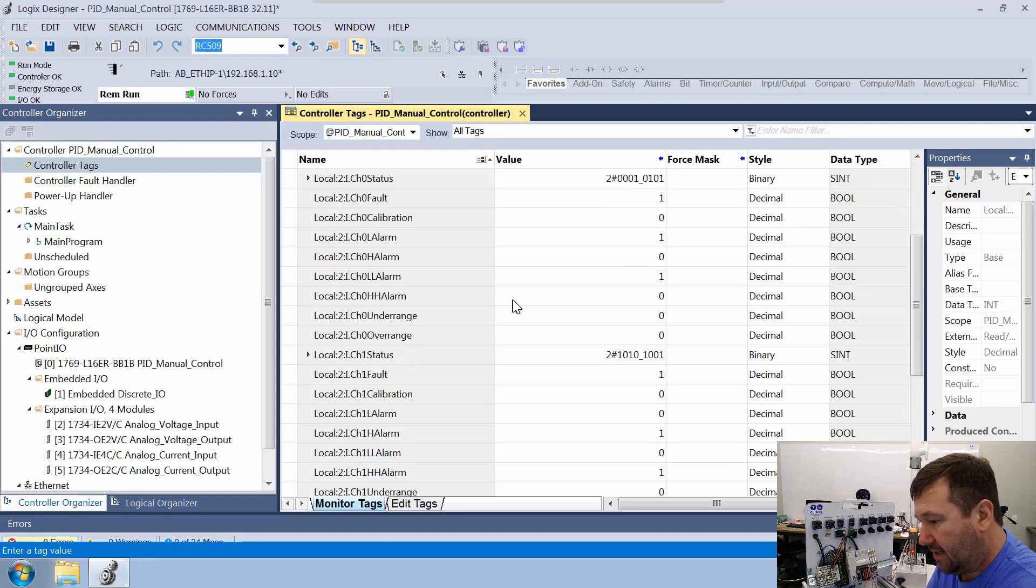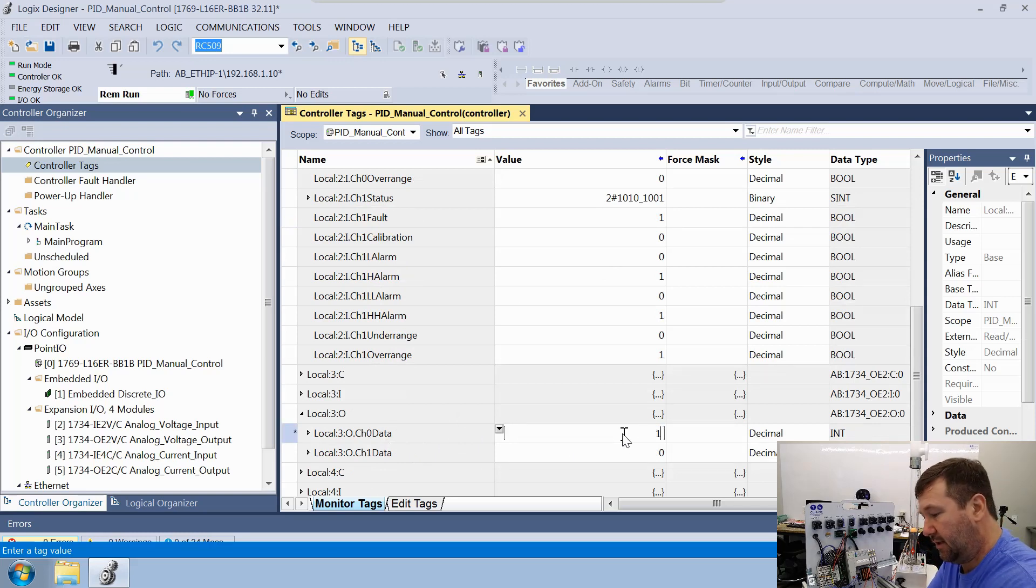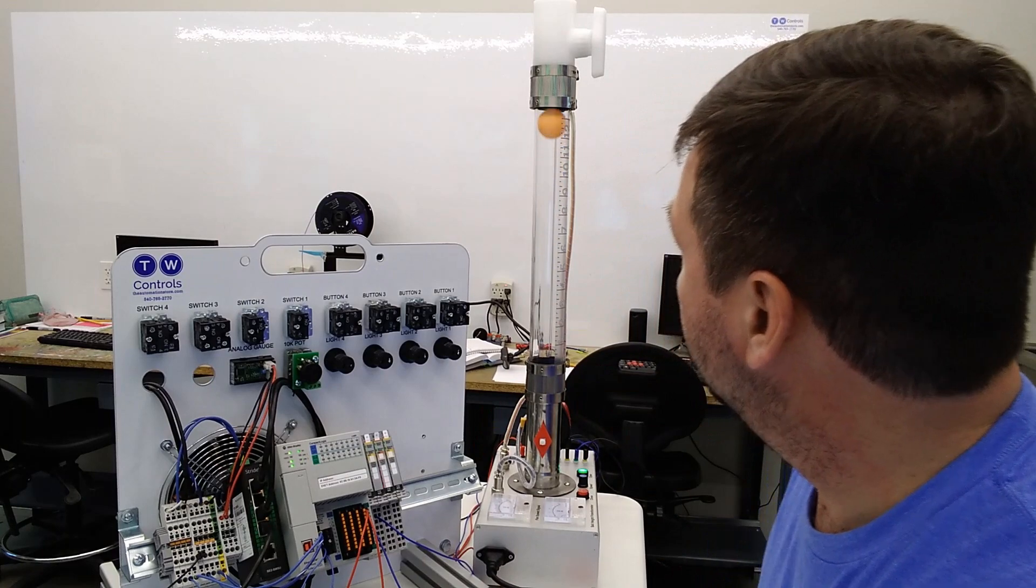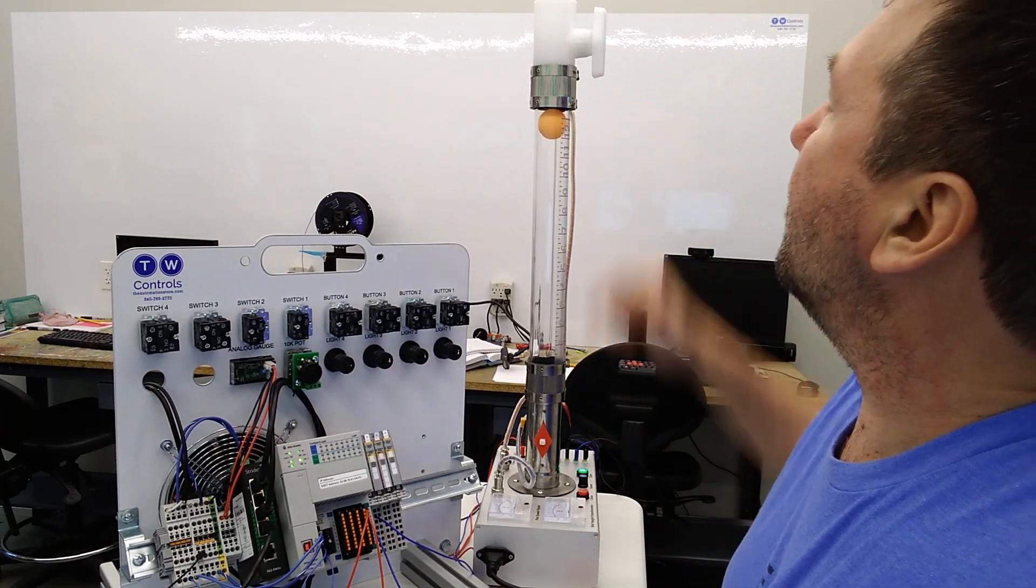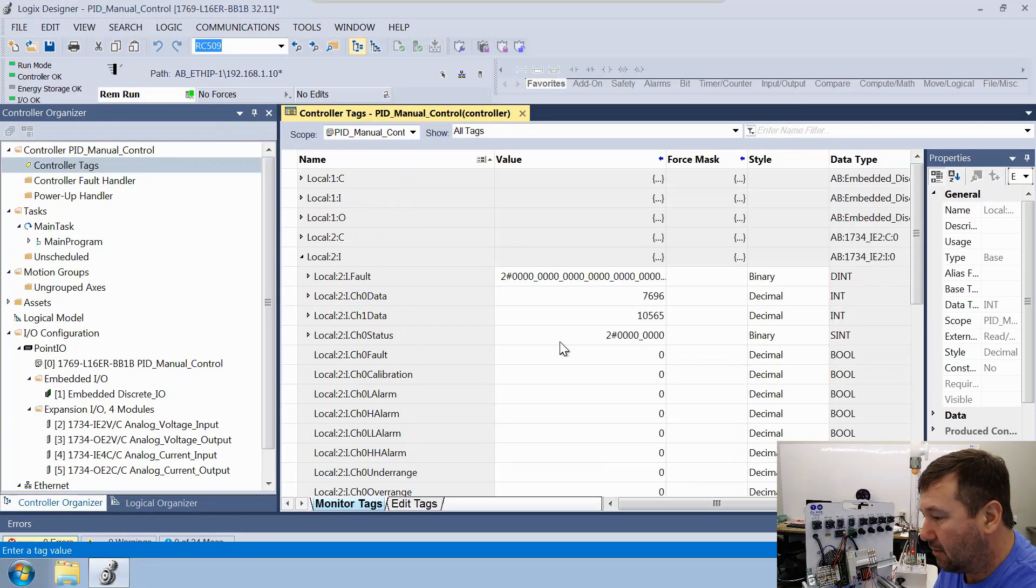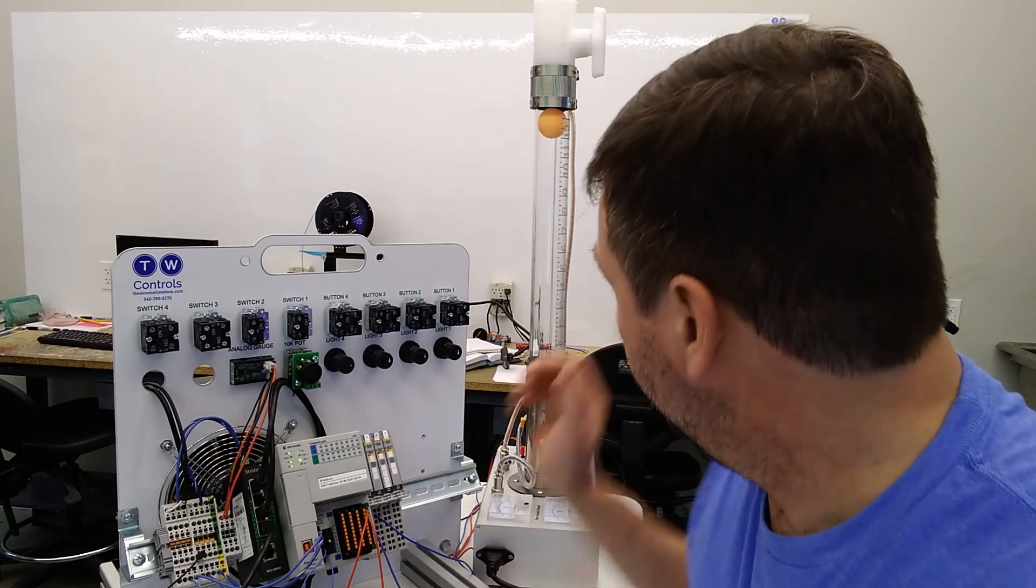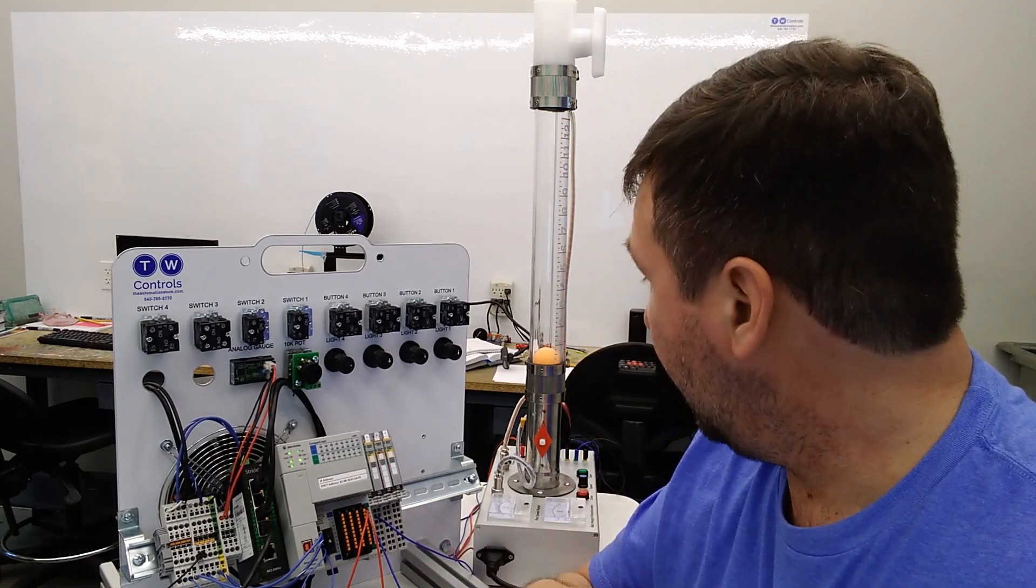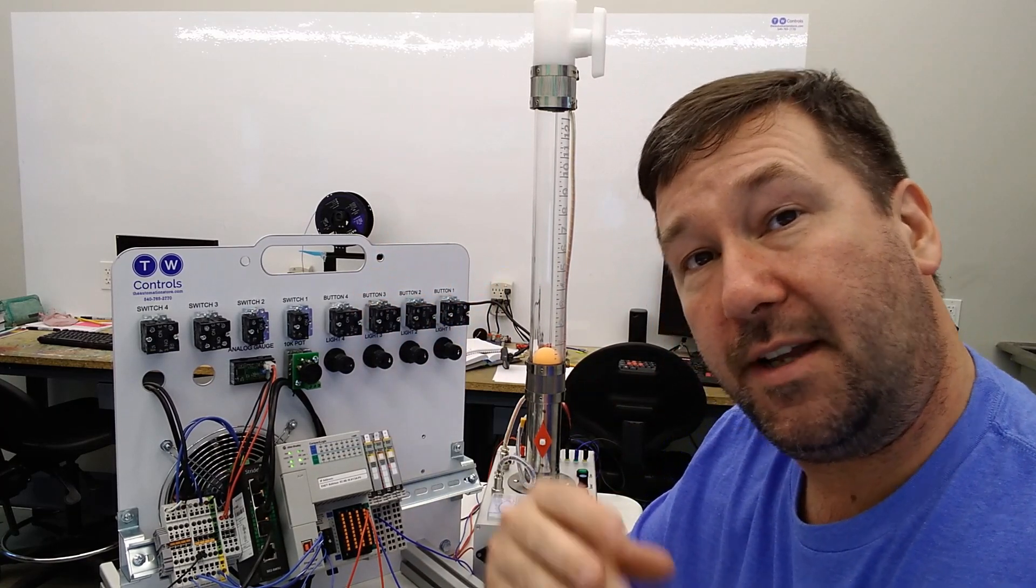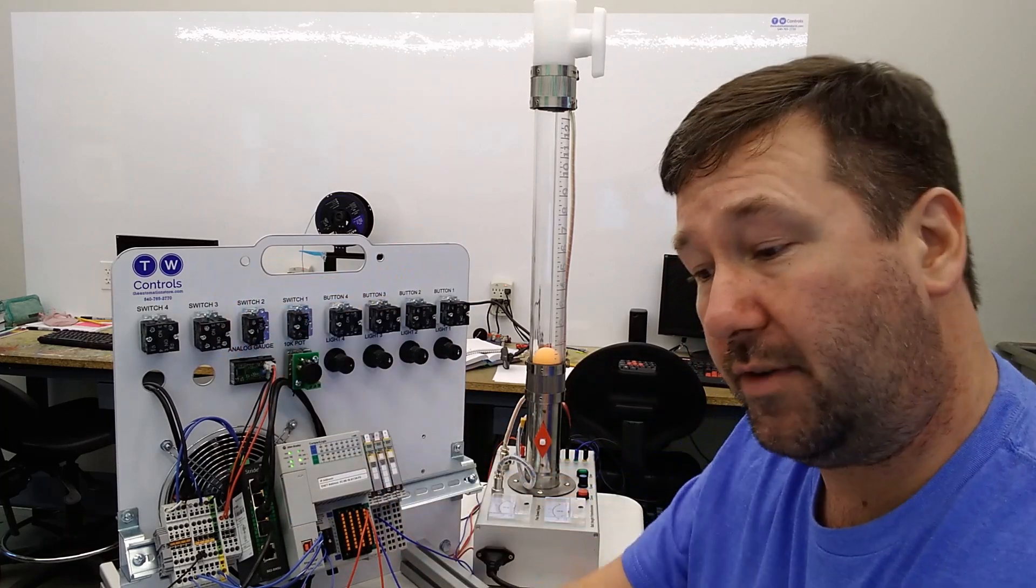Now let's figure out what our high one is. We're going to go back down to local:3:O, channel 0, and that is our analog output, and we're going to put 10,000, which is 10 volts. Then we're going to turn it on. I would call that right at about 12 inches on our scale. Let's see what our value is now. Let's call that 7,700. So the low range of our scale is going to be 400, and our high range is going to be 7,700. Now we want to scale that from 0 inches to 12 inches.